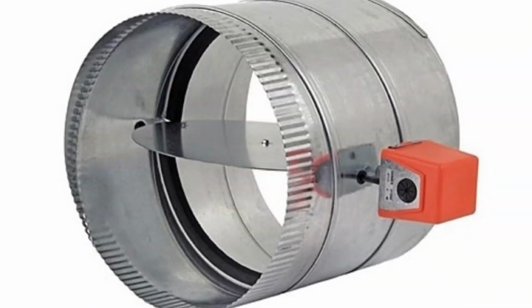There's a wide variety of quality in the zoning world. It starts with the very bottom when you have spring dampers. Spring dampers are dampers that are motorized, but then they spring closed or open depending on how they're set up. Now, spring dampers take a lot of force to open and close against that spring. Therefore, they wear out very quickly. They also use a lot more energy than a power open, power closed damper.